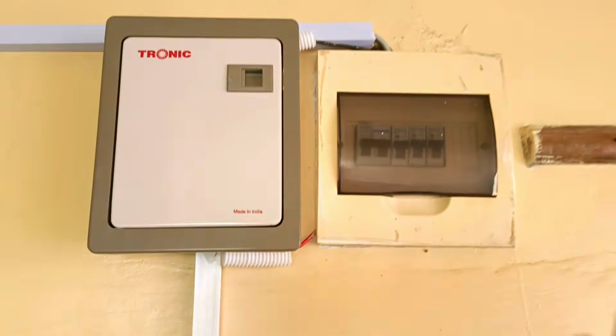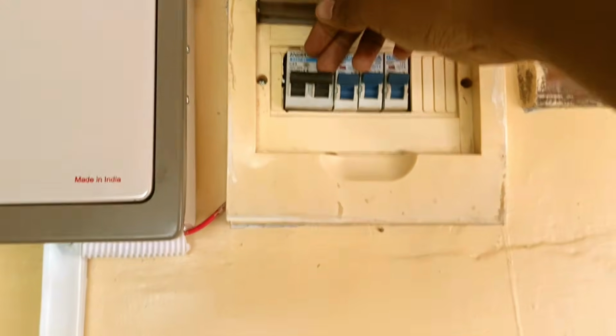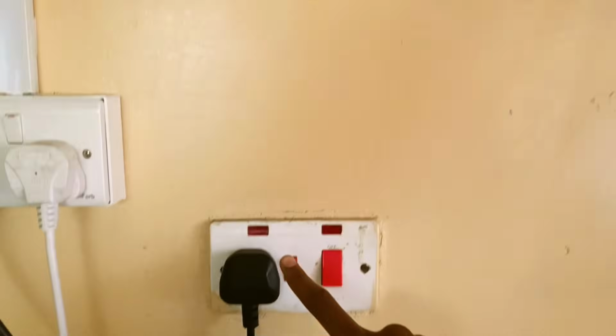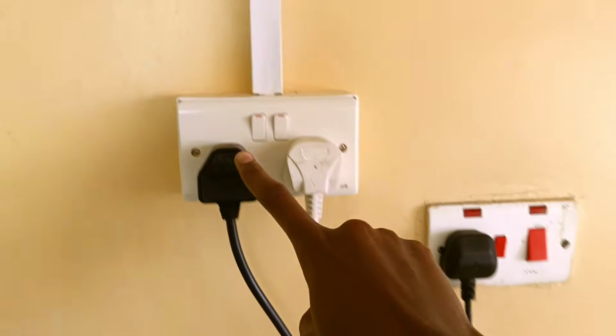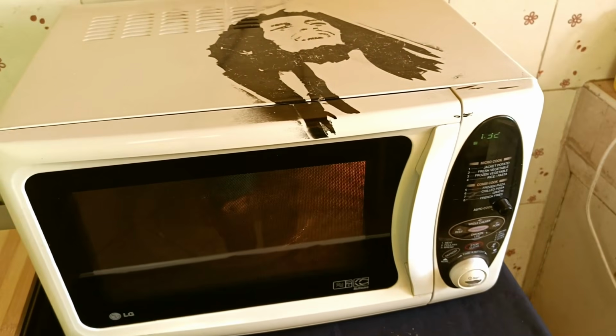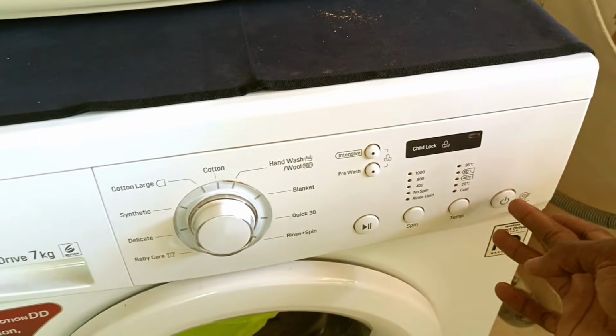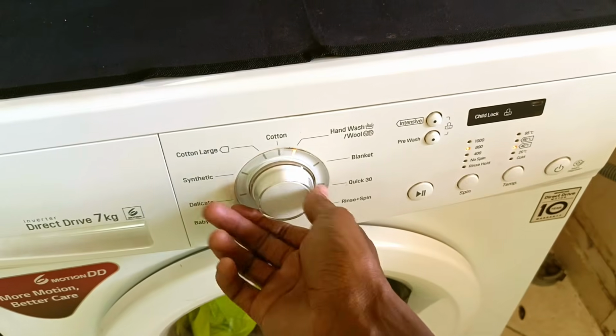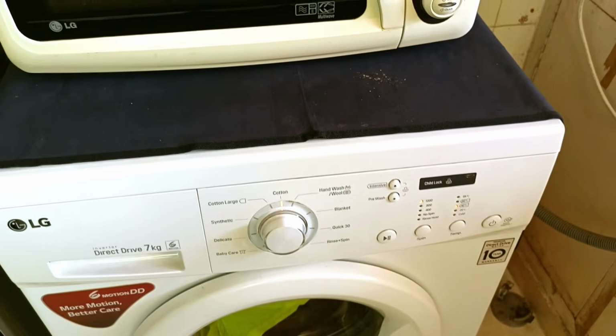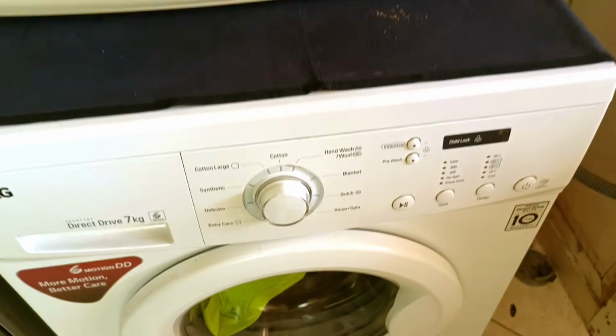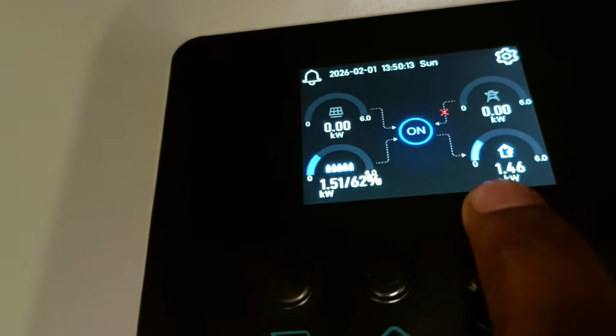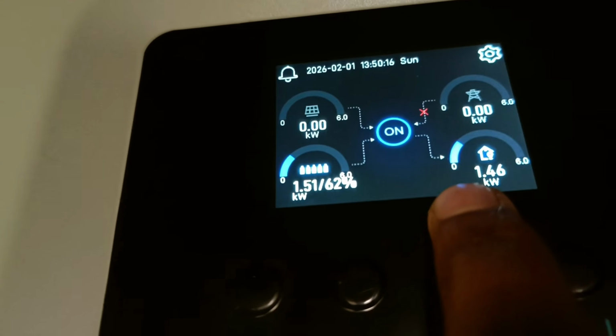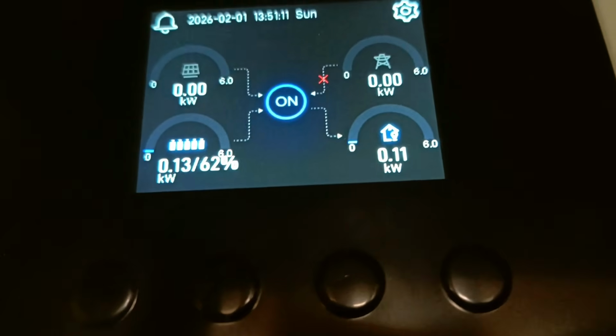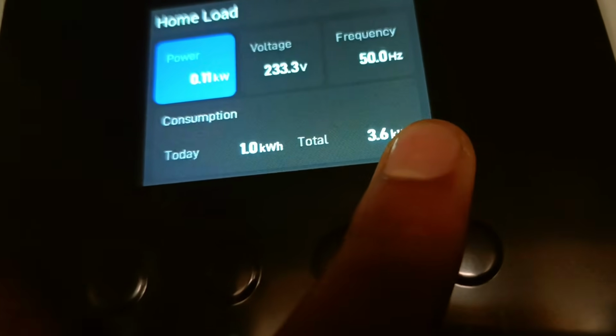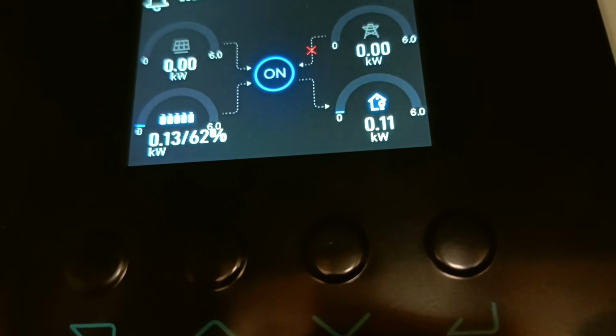And I'm going to simulate a power blackout right now by switching off this breaker. That has turned off, but my microwave is still working. The washing machine can also work. I have been using it too, and I'm very pleased with that. This shows that the microwave is pulling 1.46 kilowatts from the battery. You could hear the microwave beeping in the background, and there the consumption has gone down to 0.11 kilowatts.